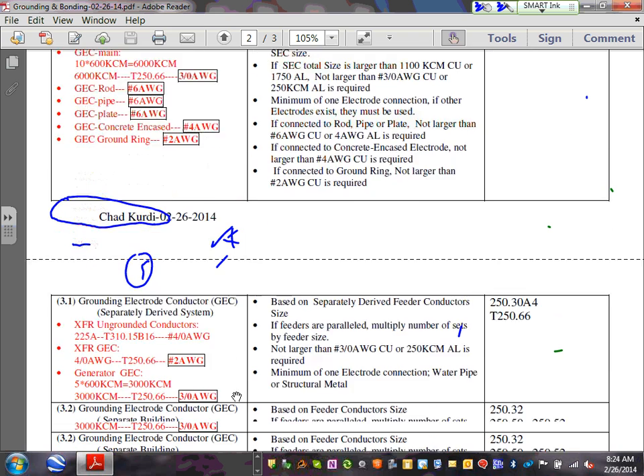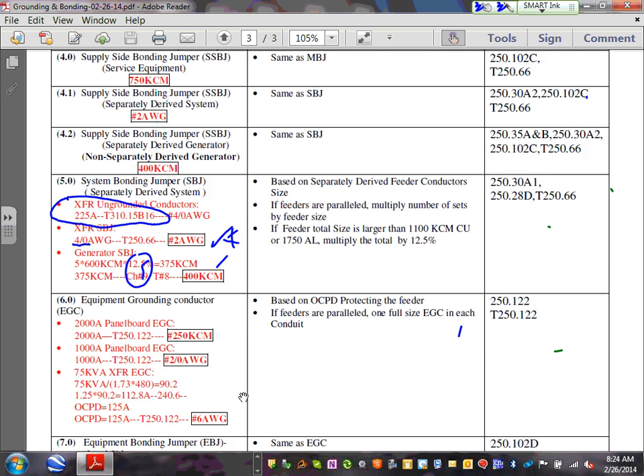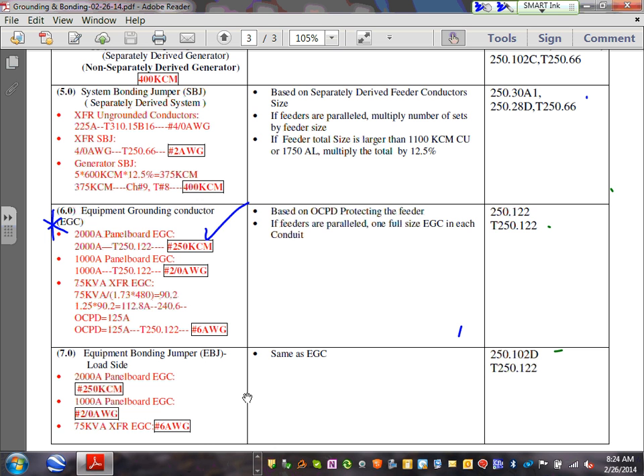So let's go to number 6, the equipment grounding conductor of the second building. Karen, the equipment grounding conductor of the second building, I was actually looking at it accidentally. At the second building, here's how we size it based on 2000 amp. At the same building, which I should have been talking about before, 200 amp. Can you guys see that? The equipment grounding conductor for the sub panel in the same building should have been 200 amp, actually, and the second building is 250. So you take the 200 amp, take it to 250.122, and you size your equipment grounding conductor.